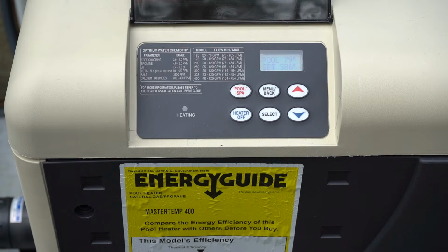Number two is if something is blocking the actual air going into the heater. So let's just say that this heater was installed indoors and they didn't have the proper ventilation. So now you don't get the proper flame because it doesn't have enough air to actually ignite it correctly. And so that will cause it to soot. However, this heater is outside. I have a FlowViz meter on it, and it is always set so that it comes on, that it's set to 50 gallons a minute. And so we don't have a flow issue, and we do not have an air issue or an airflow issue. So we're down at that point to the gas pressure is incorrect. And more than likely the gas pressure is incorrect on what's called the manifold side.